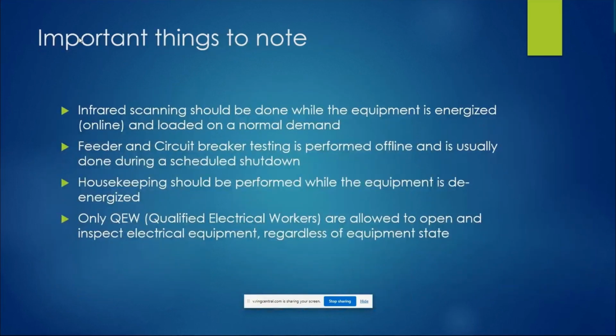So, things I want you to note from this presentation: infrared. This should be done while the equipment is energized, loaded, and on normal demand schedule. It's not going to do you any good to do an infrared scan on something that's turned off. You're going to get no heat signature. So it needs to be on a normal work day.